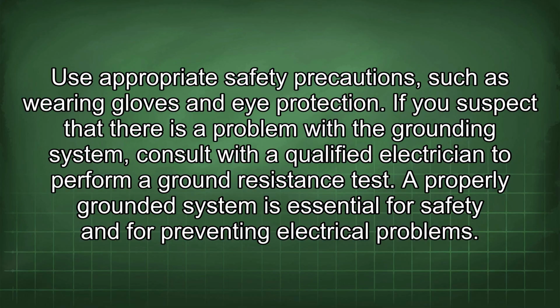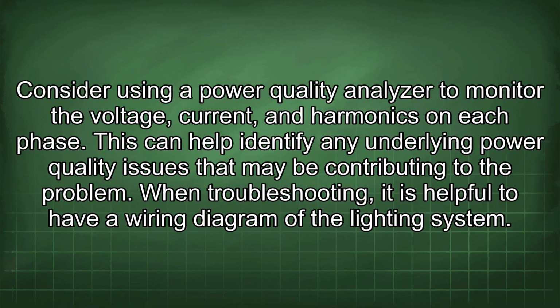If you suspect that there is a problem with the grounding system, consult with a qualified electrician to perform a ground resistance test. A properly grounded system is essential for safety and for preventing electrical problems. Consider using a power quality analyzer to monitor the voltage, current, and harmonics on each phase. This can help identify any underlying power quality issues that may be contributing to the problem.